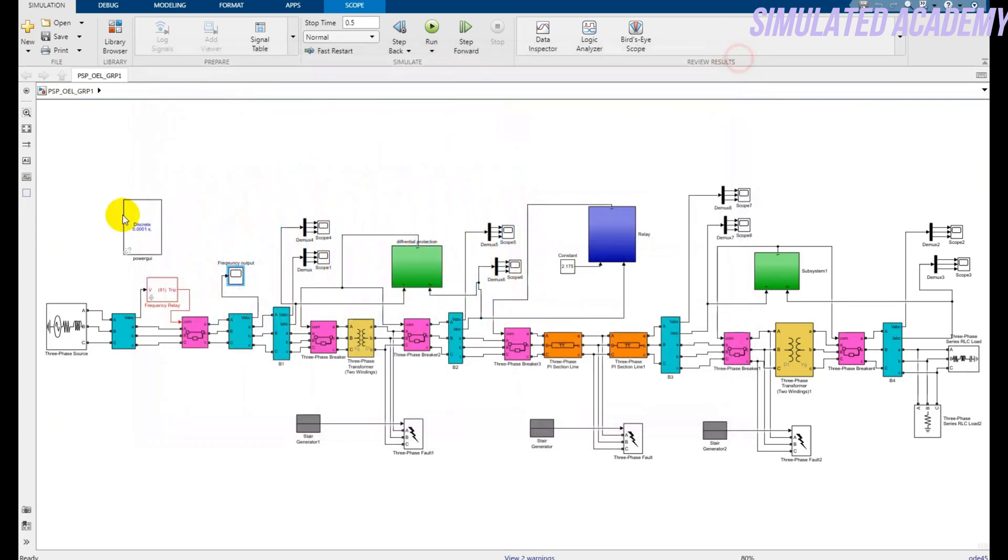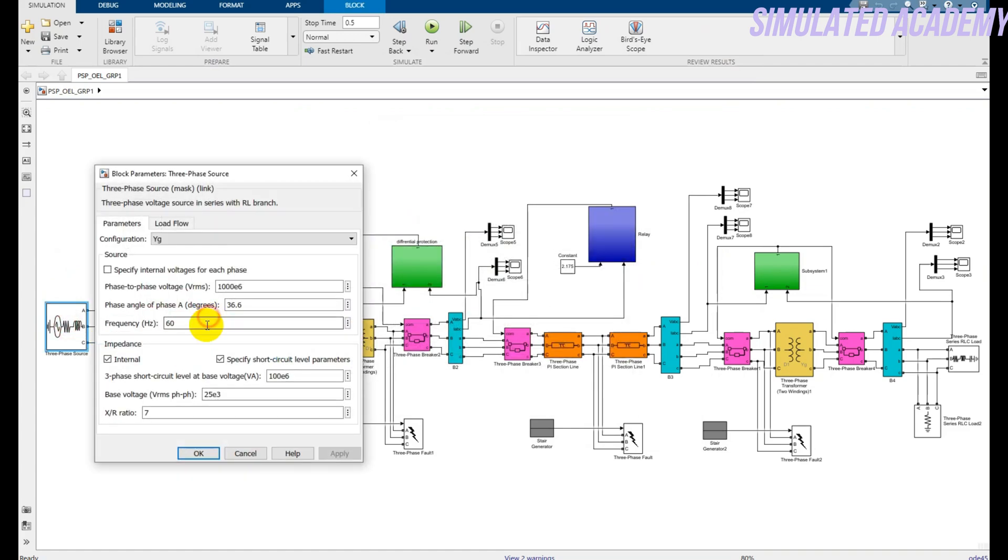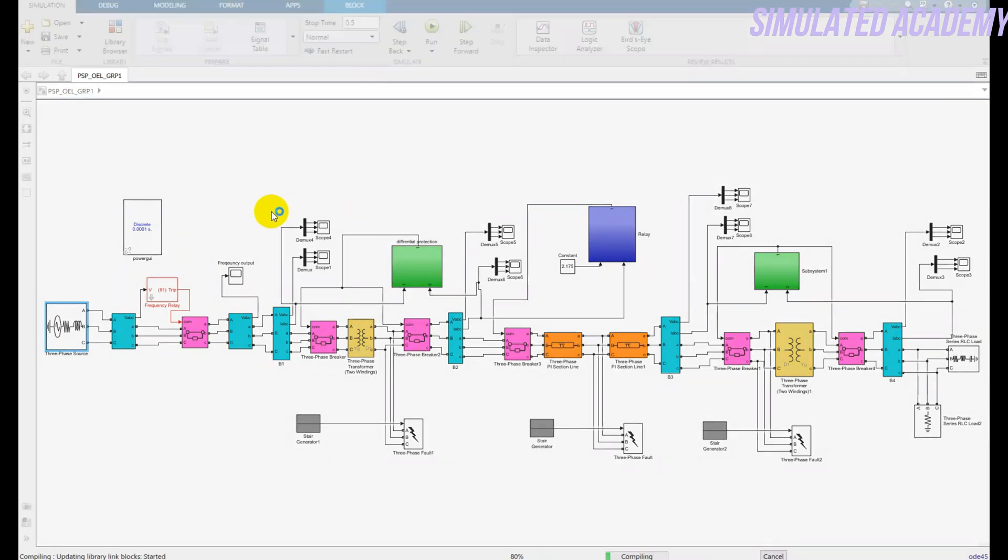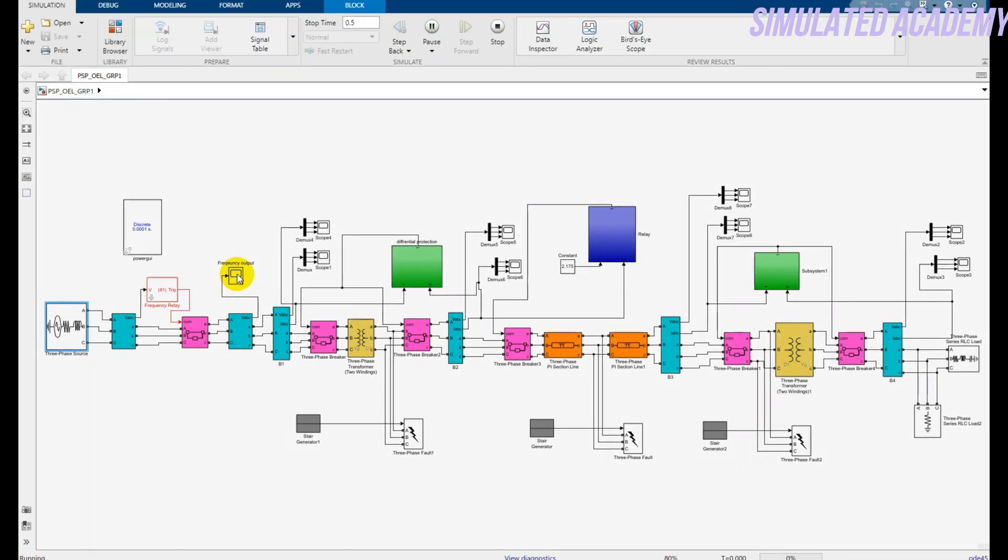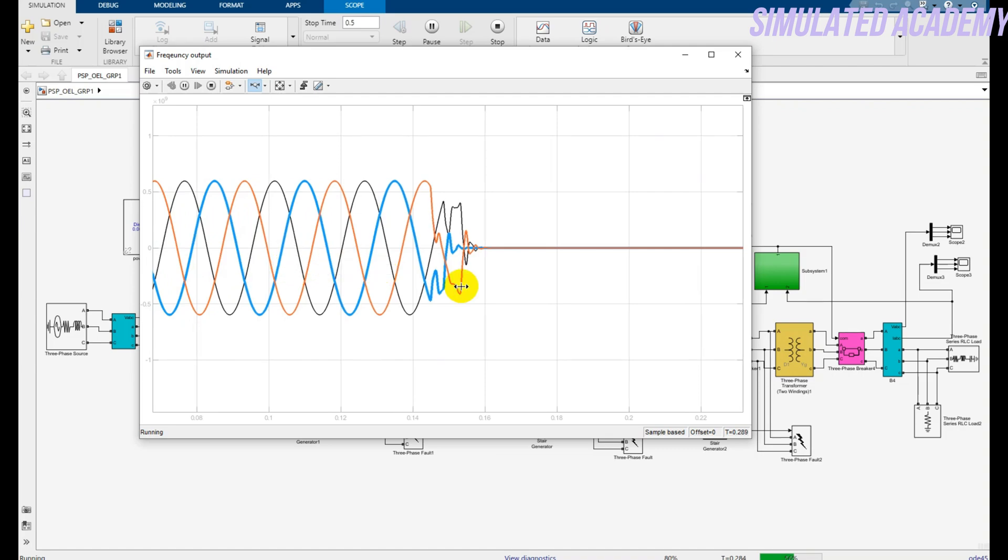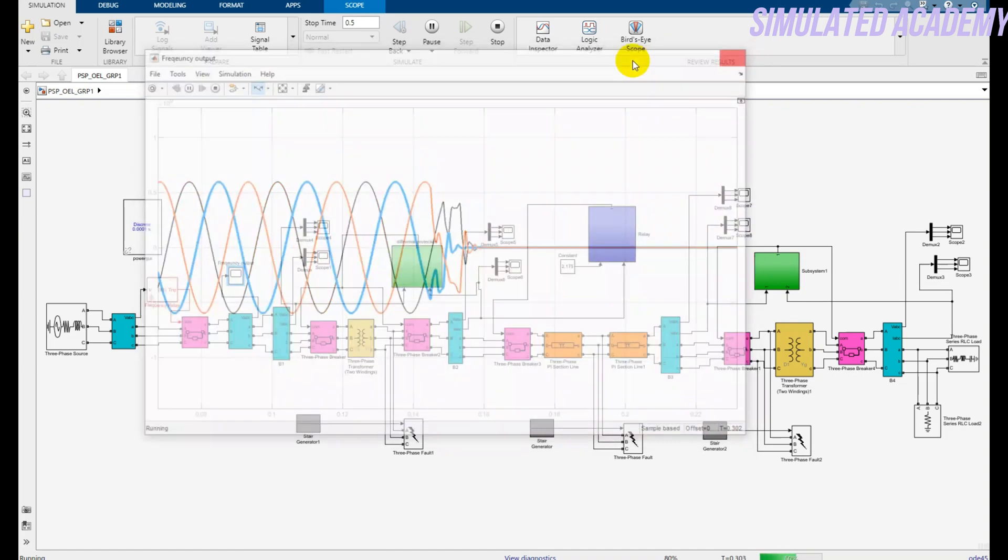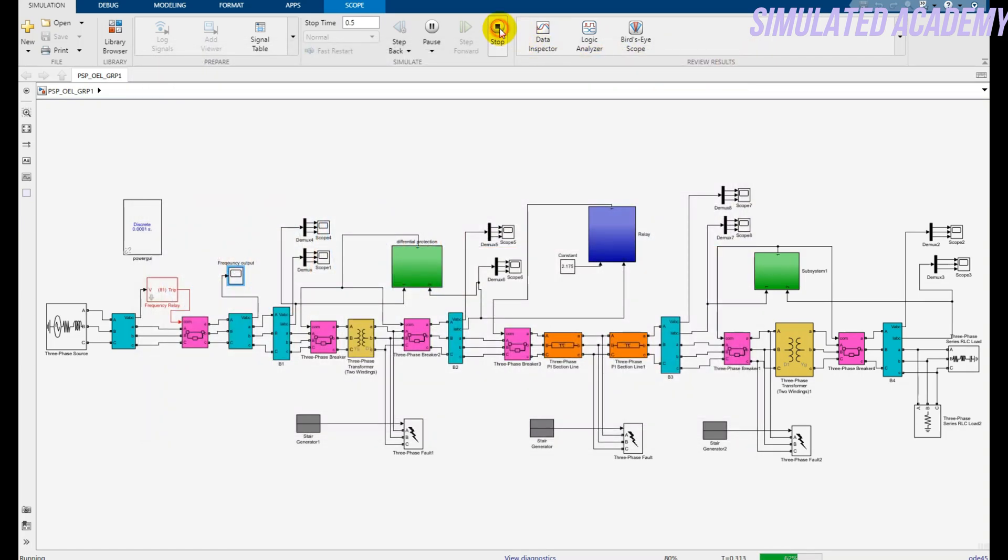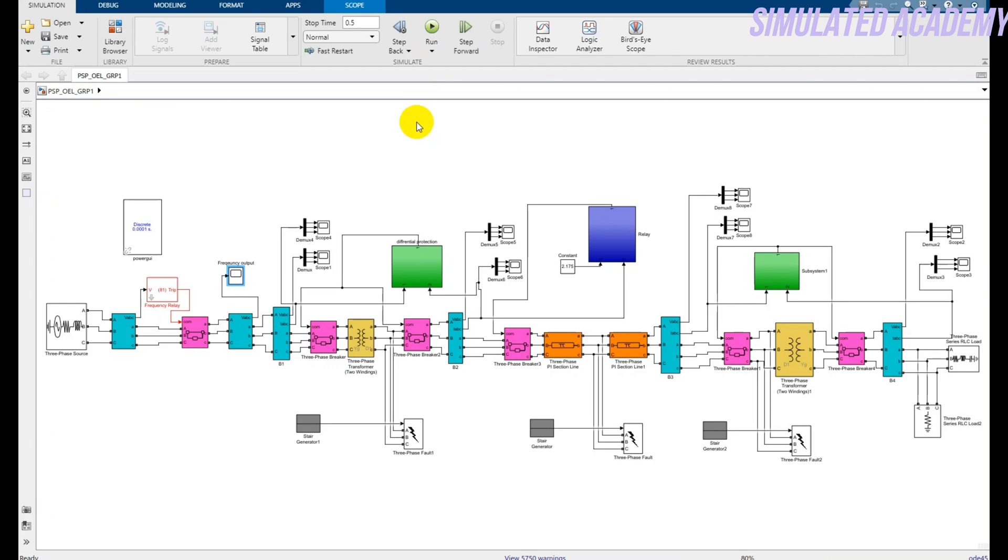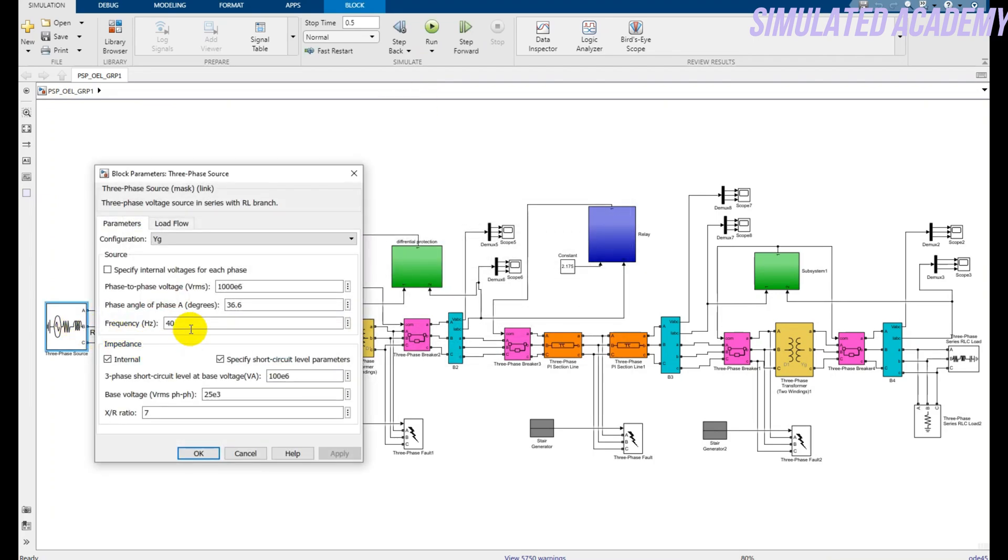Now if I change the frequency from 50 to 40, then it should also operate. It will take a very short time because it's a very heavy program. Double click on this. Here it is, it operates. So if the frequency is out of the range, that is plus minus 1% of the nominal frequency, then it will operate.